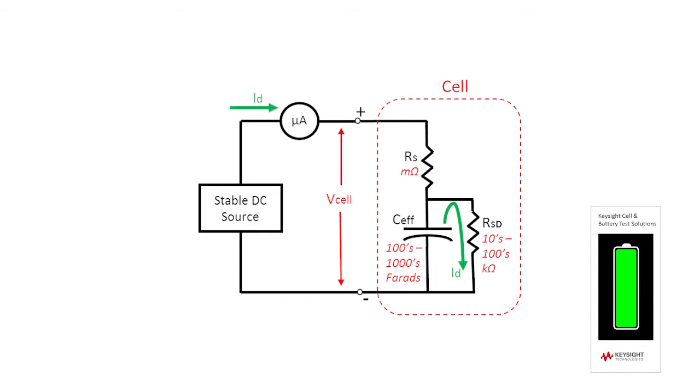The potentiostatic method also uses a microammeter to measure the small amount of current flowing from the DC source to keep the cell voltage constant. As long as the cell's voltage is constant, the current flowing from the DC source into the cell is equal to the cell's self-discharge current, I-sub-D, flowing through R-sub-SD.